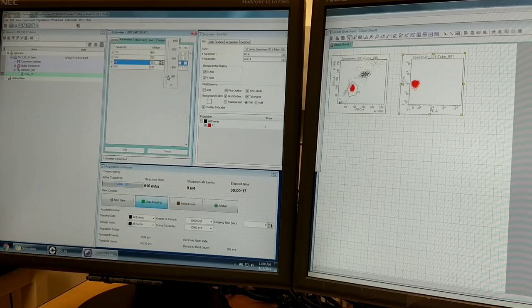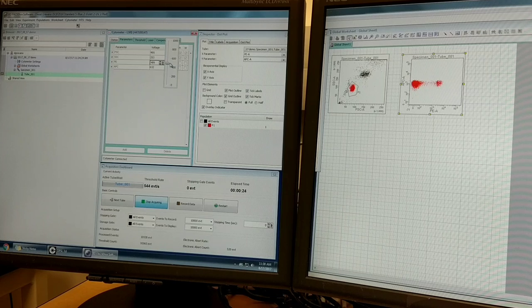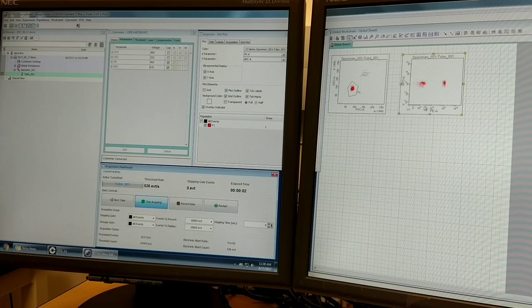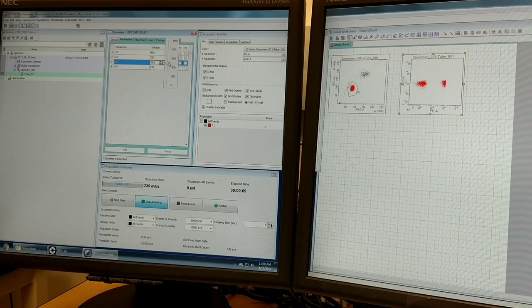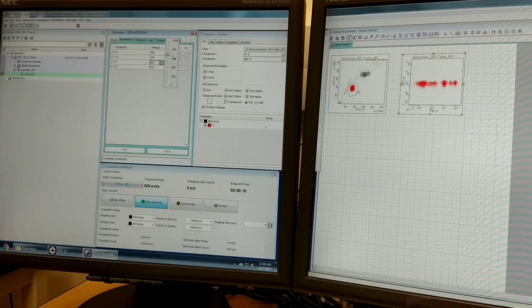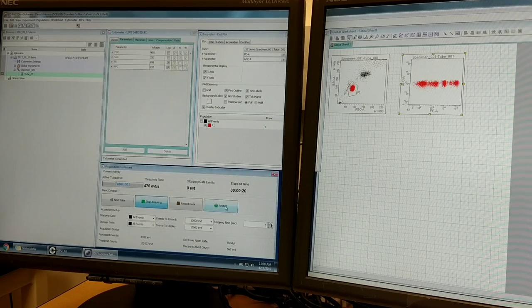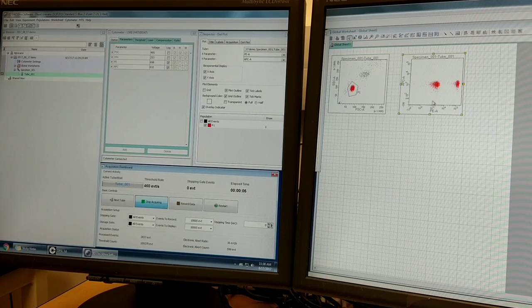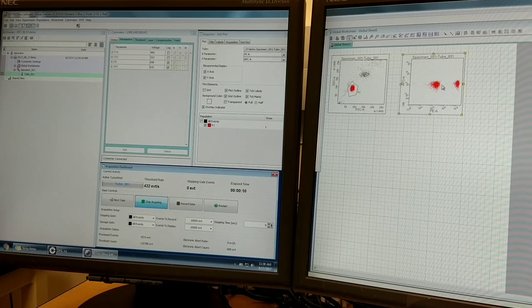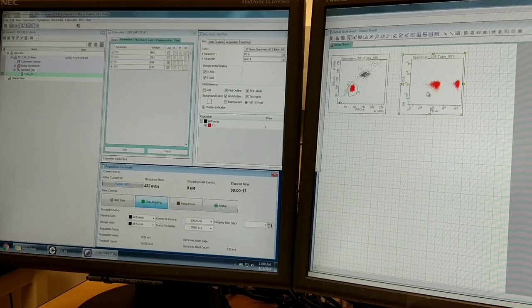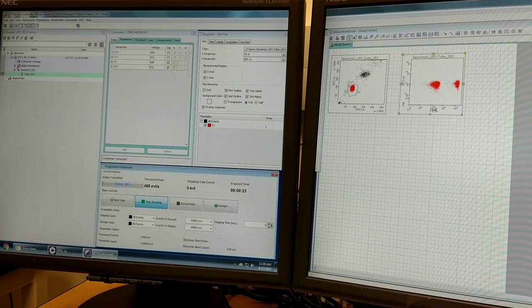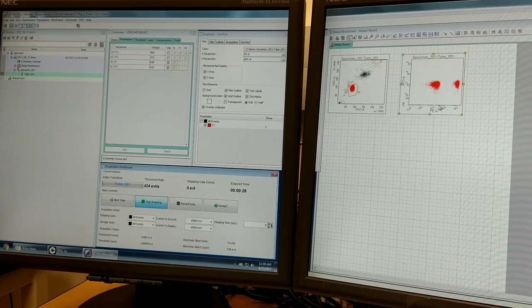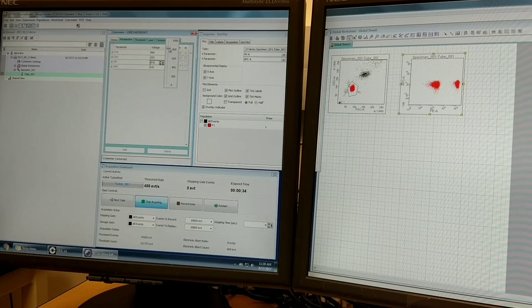You want to have that discrimination. We were seeing pretty good discrimination probably in the 400 to 500 range. Let's go back up to 500. Now we can see about a 2 log shift, which looks pretty good at 495. Now I can go up even farther and show you another extreme. Let's pull this up to 700. I'm almost off the chart here with my positive population, and you'll notice my negative population is now at 10 to the third. I still only have a 2 log shift in my data. So there's no greater separation at this voltage setting of near 700 as there was at 500. This is no advantage, and it's increasing my background to above 10 to the third, which I start to consider unacceptable.